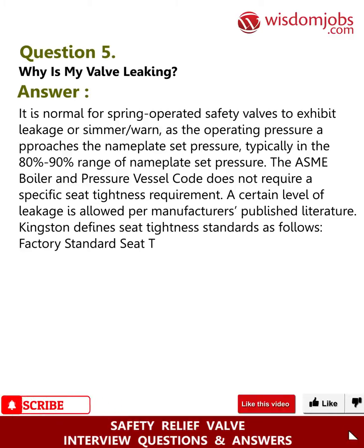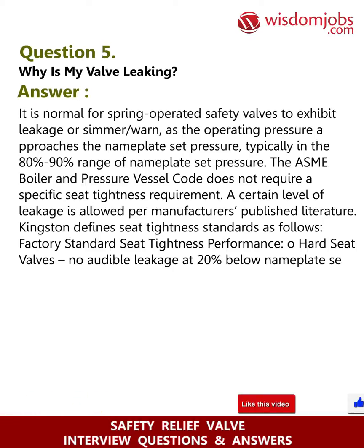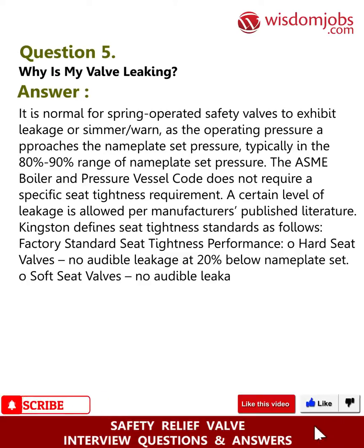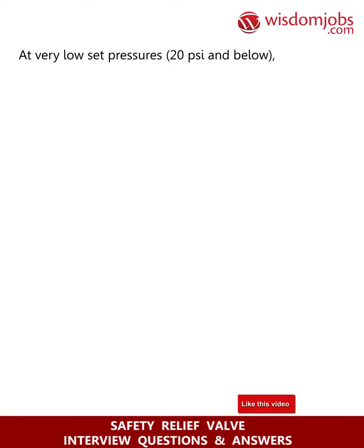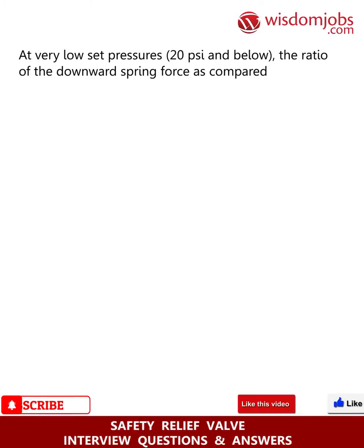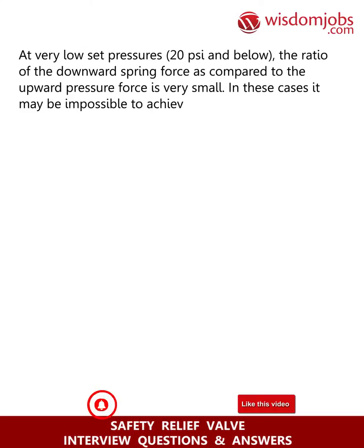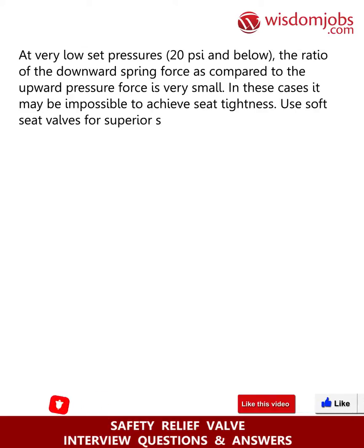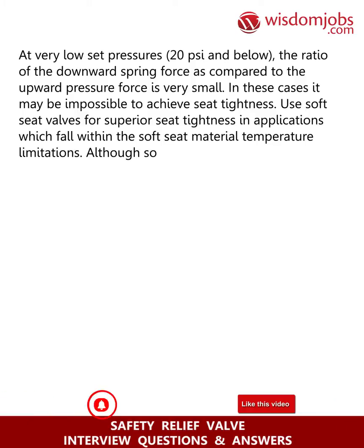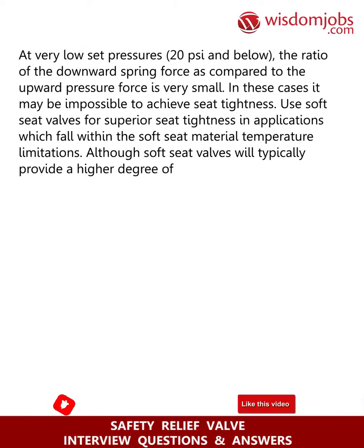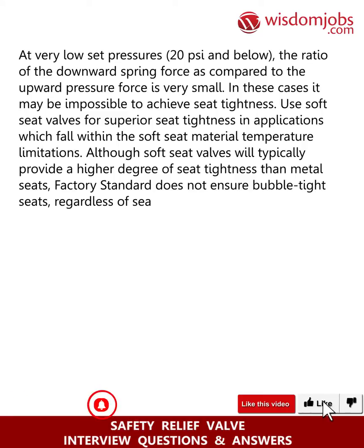A certain level of leakage is allowed per manufacturer's published literature. Kingston defines seat tightness standards as follows — factory standard seat tightness performance: hard seat valves, no audible leakage at 20 percent below nameplate set; soft seat valves, no audible leakage at 10 percent below nameplate set. At very low set pressures (20 PSI and below), the ratio of the downward spring force compared to the upward pressure force is very small; in these cases it may be impossible to achieve seat tightness. Use soft seat valves for superior seat tightness in applications within the soft seat material temperature limitations. Factory standard does not ensure bubble-tight seats regardless of seat material.